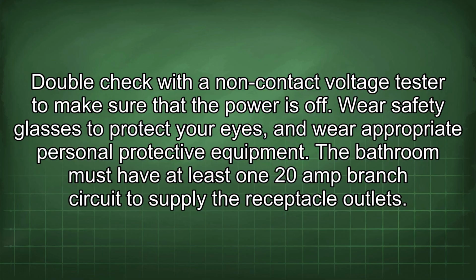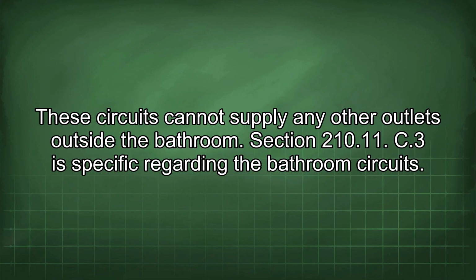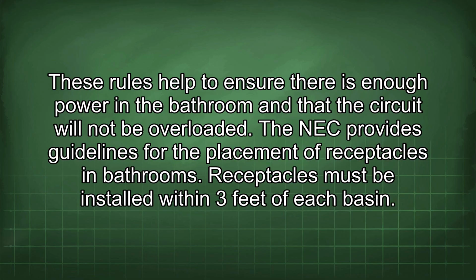The bathroom must have at least one 20-amp branch circuit to supply the receptacle outlets. These circuits cannot supply any other outlets outside the bathroom. Section 210.11 C3 is specific regarding the bathroom circuits. These rules help to ensure there is enough power in the bathroom and that the circuit will not be overloaded.